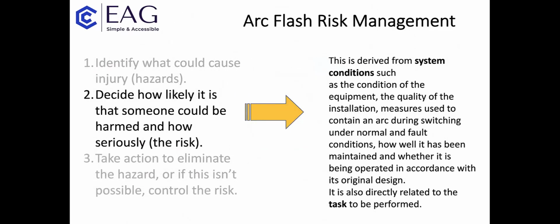And secondly, in our very simple list, we have to consider how likely it is that somebody could be harmed and how seriously. In other words, this is what the risk is, isn't it? For arc flash, it's derived from system conditions, such as the condition of the equipment, the quality of the installation, measures used to contain an arc during switching under normal or fault conditions, how well it's been maintained, and whether it's been operated in accordance with its original design. But very importantly, it's also directly related to the task to be performed and whether you should be there in the first place.